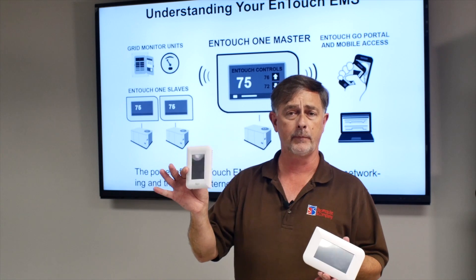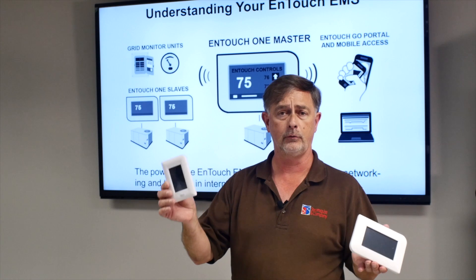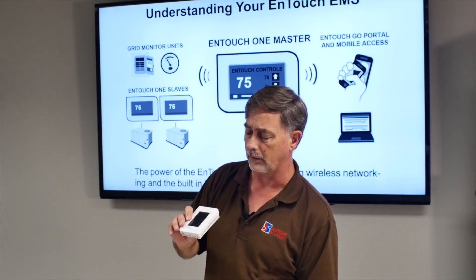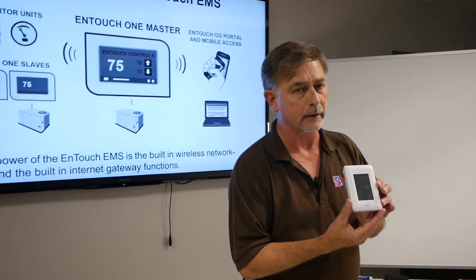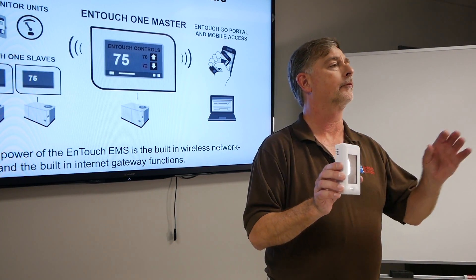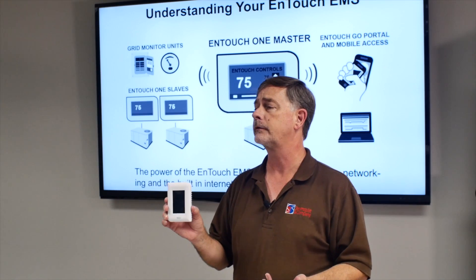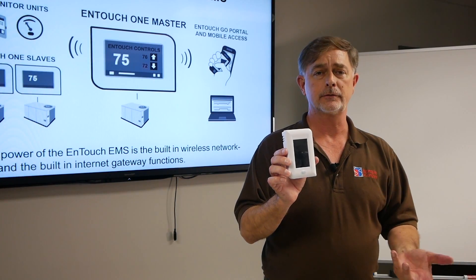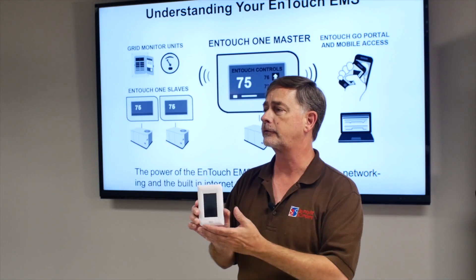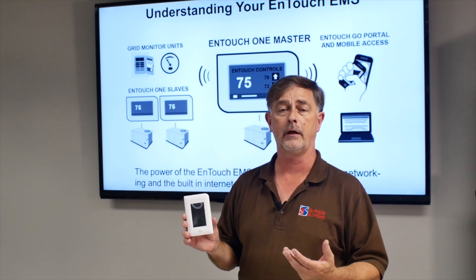The EnTouch One is a Wi-Fi based thermostat. It controls up to two stages of heat, two stages of cool. It also has a wonderful little option right here if you look at this lens — this is a motion sensor. So you can have this programmed for occupied and unoccupied times. And then let's say someone comes in after hours — this sees the movement, changes the set points to occupied, and then when they leave, this goes back and sees no more movement, and you're back to your setback temperatures.